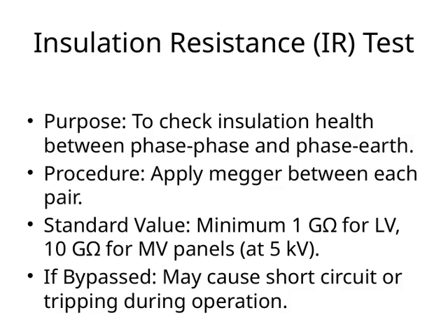Let's talk about the insulation resistance, or IR, test. The main purpose here is to ensure the insulation health between the phases and between the phase and earth. This is crucial because good insulation prevents unwanted current leaks and potential failures. The procedure involves applying a megger between each pair of conductors. So, you test phase to phase and phase to earth, making sure everything is properly insulated.